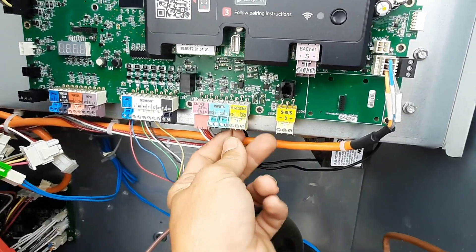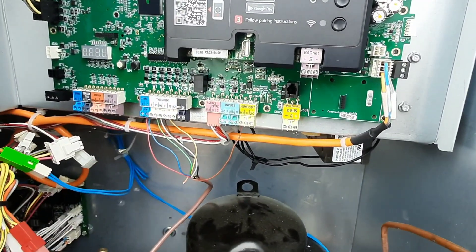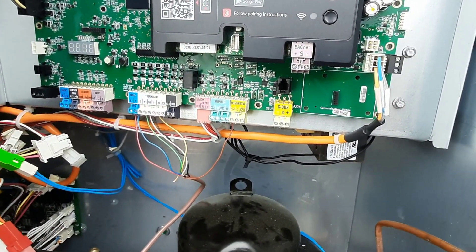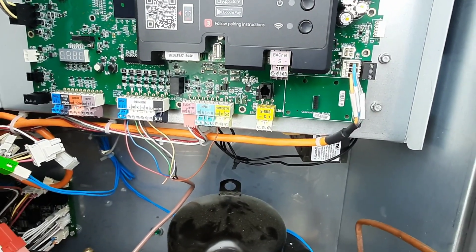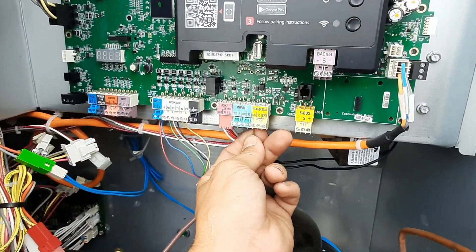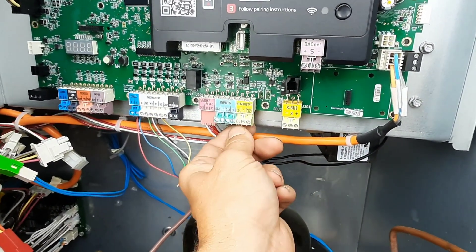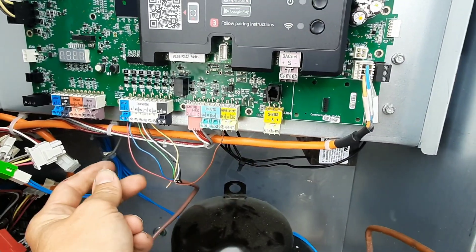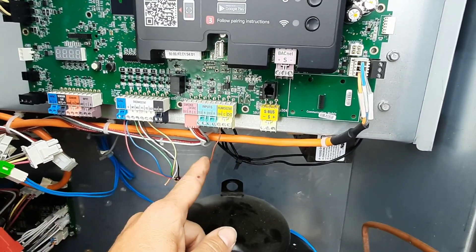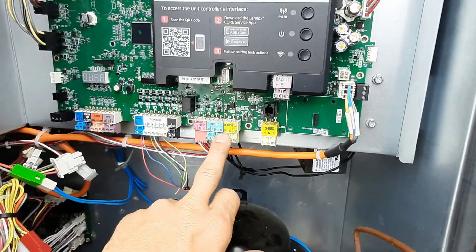What I found was on the Lennox thermostats they have to be set up for it, but you can program them for D-hum. They've got a Humiditrol setting — set it to Humiditrol, and land a wire from the D terminal on the thermostat to DI4, which is your digital input. That's going to give it the D-hum call.